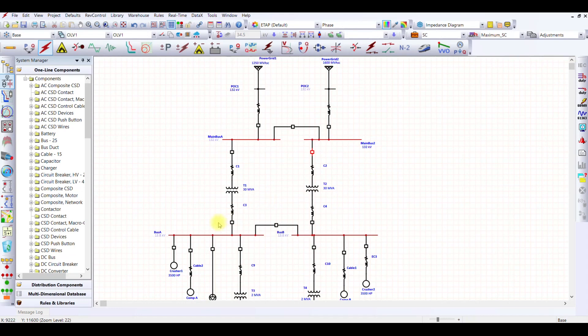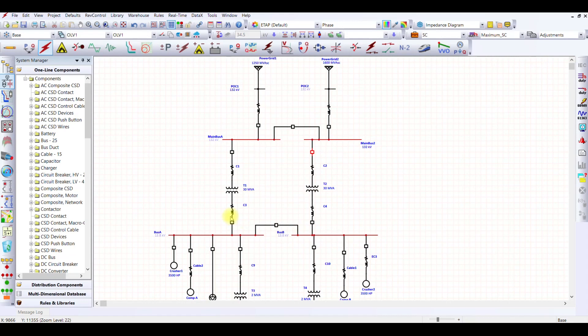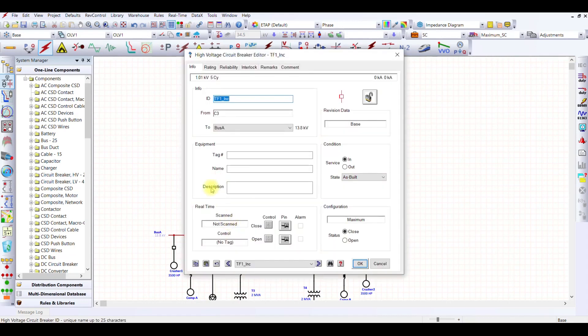For my 13.8 kV, my short circuit level was 29.146, so I need a kind of breaker which should have a capability more than at least 29 kilo ampere, or 29 multiplied by 1.1 is around 32. So at least 32 kilo ampere. For this, I'm going to click on this breaker, then I'm going on the rating.